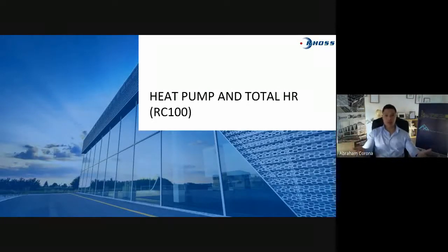We are not calling this polyvalent. We are not calling this multipurpose. So we got a specification where it was specified a reversible heat pump. All right, a reversible heat pump is a standard heat pump. A reversible heat pump with heat recovery, that was what it's called. All right, but we know that a reversible heat pump with a heat recovery standard controller is not the same as a polyvalent EXP heat pump.